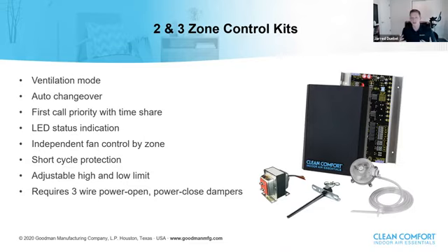So typically in a zone control system, we recommend you run continuous fan. And what that means is when all zones are satisfied on a traditional zone control system, all those dampers are just going to go to the open position. When we're running ventilation mode, we're running the fan in low speed, we're slowly just ventilating air all throughout that zone system. Well, what we do is we take it to another level. We say, well, why not prioritize where we want to ventilate? So it's a very simple way that you can do so. It's set through the actual thermostat.